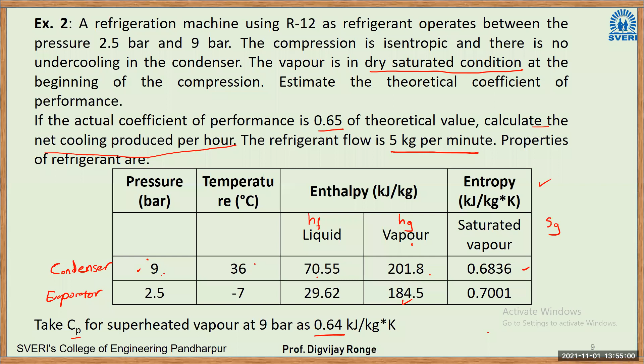Once again, I will repeat how we have calculated this. You have a problem: condenser pressure is 9 bar, 2.5 bar is the evaporation pressure. They have given the enthalpy and entropy values. Then you have to calculate the COP. H1 and H4 are easily calculated from the given data, but H2 takes some extra effort. For H2, the enthalpy at the exit of the compressor, we need to know the temperature at the exit of the compressor, so T2 also needs to be calculated. For T2, you have made use of one property, that is the isentropic process. Before and after the compression, S1 will be equal to S2, so the entropies remain the same. From that we calculated T2, from T2 we calculated H2, and from that we calculated the COP.